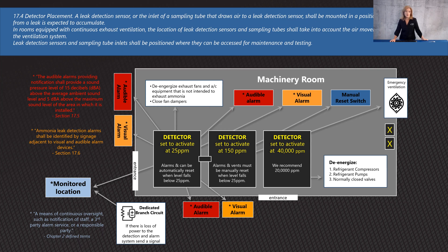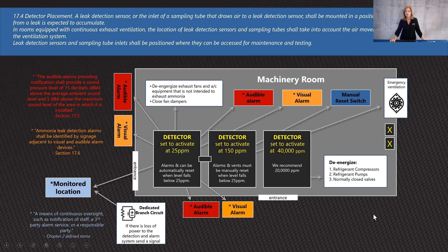IIAR also cares about where you locate these detectors. They need to be placed in the path of the ammonia — if ammonia is in the room, think about how it's going to flow, usually towards your fans. So it's a good idea to put them near the fans. They also have to be in a place that's easily accessible for maintenance and calibration. We recommend putting them in the breathing zone, about five feet up off the floor.